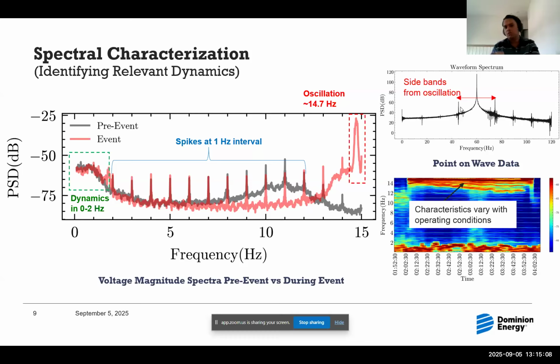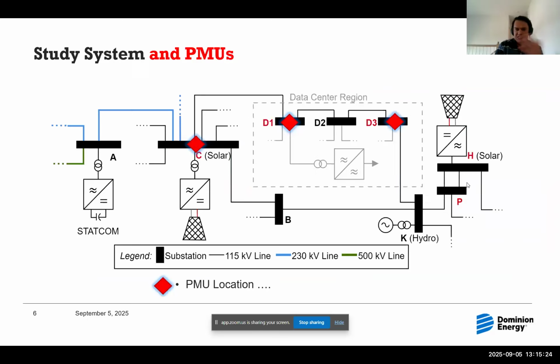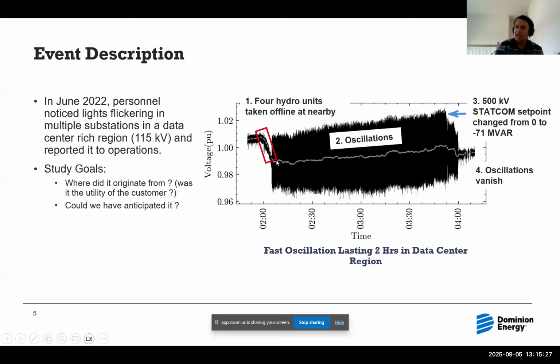Okay, and another clue to gather from this particular event is that this oscillation, which is happening for 2 hours, is responding to operating characteristics of the system. What I mean to say is that if you look at the DC part or the slow part of the voltage magnitude here, you'll see how when we took the generators offline, the voltage went down because they must be supplying reactive power. And then over a period of 2 hours, you'll see a trend in voltage magnitude. So however the operating conditions are evolving, your voltage magnitude is evolving, increasing in this case gradually.